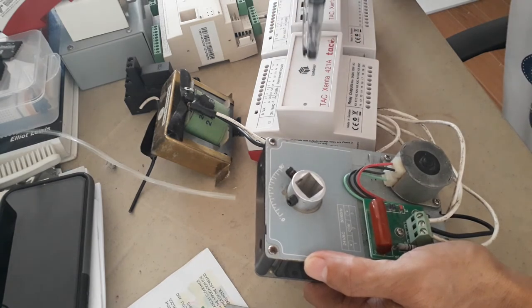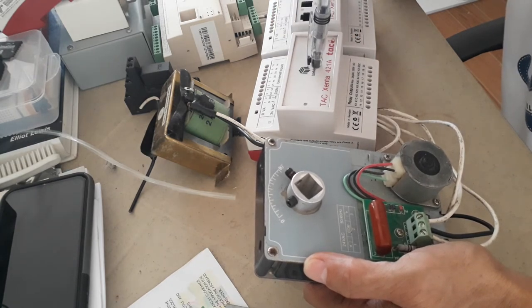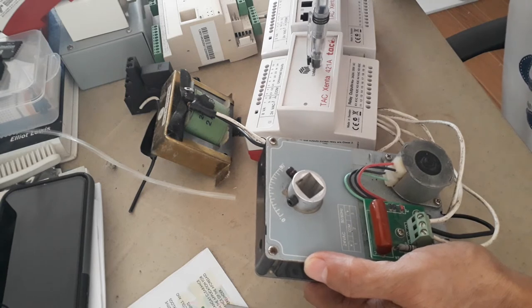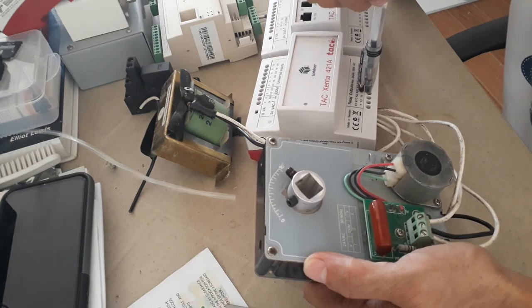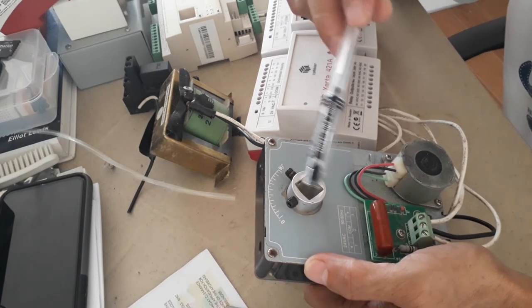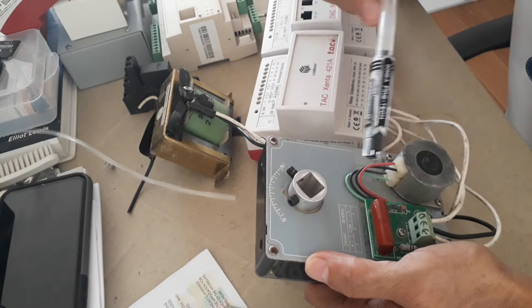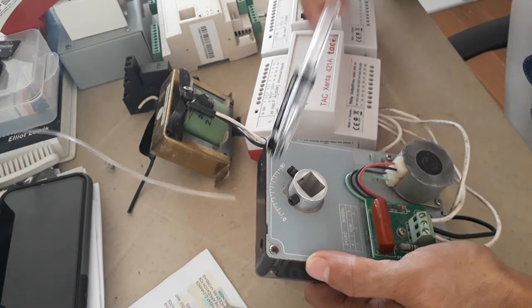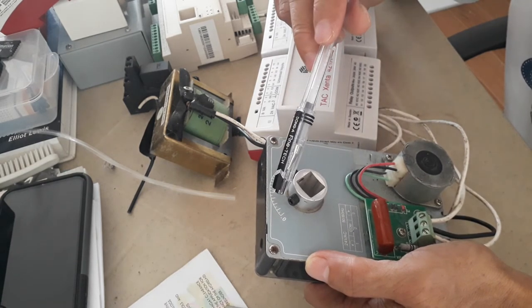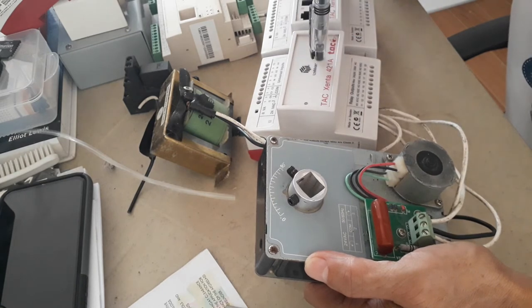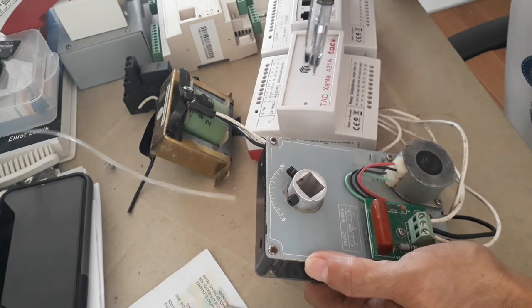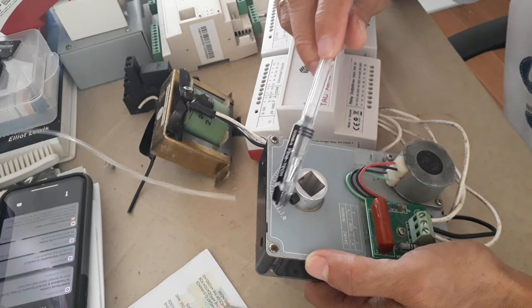Now, if my control program says you will close it at 15%, then this relay will activate this to rotate it the other way. So from 30% it will go to 15%. If there is no control signal to close it, then it will stay at 15%.